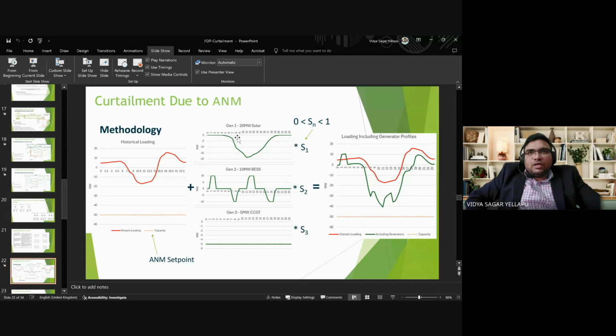On a sunny day, it will have a peak generation at around 12 p.m. It is just like a Gaussian distribution, but it is as per the solar irradiance levels at different points in time in the day. The hours are 0 to 24, and this loading is also from 0 to 24. This is the power profile of a battery energy storage system. We know that a battery energy storage system takes in power at some times and gives out power at other times. So these are the times the battery energy storage takes in power, and these are the times at which the BESS sends out power.